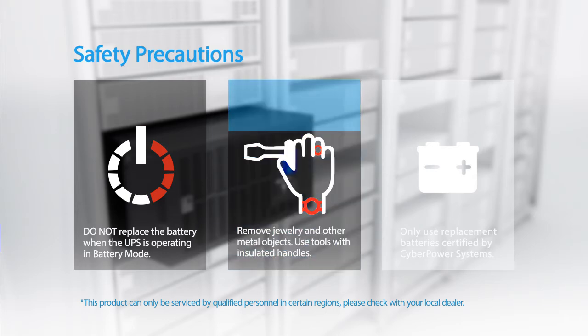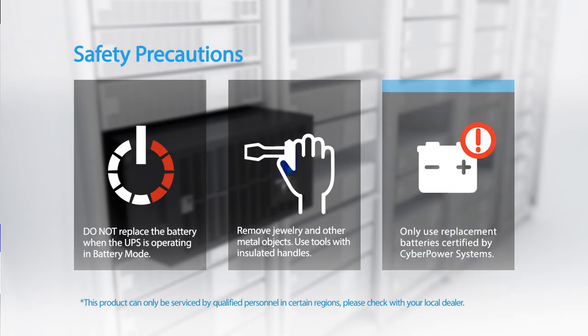The batteries for this UPS series are hot-swappable. It is not necessary to power down the UPS. Do not replace the battery when the UPS is operating in battery mode. Remove jewelry and other metal objects. Use tools with insulated handles only.